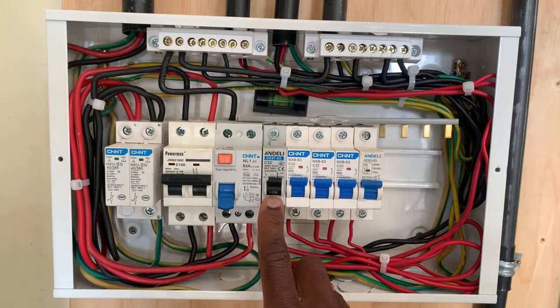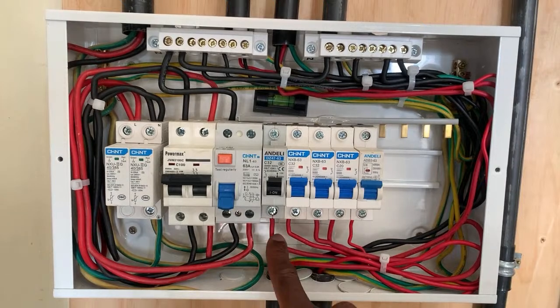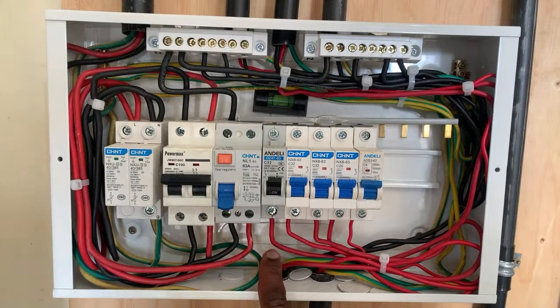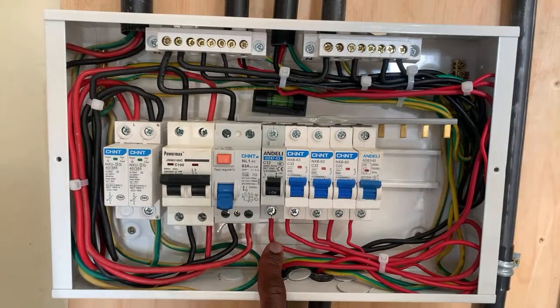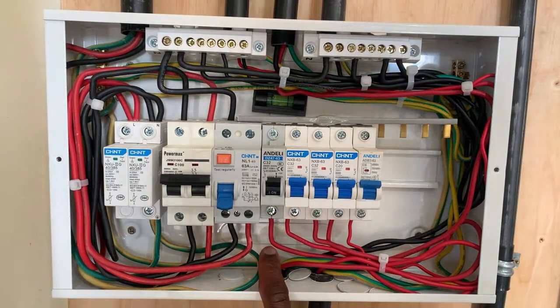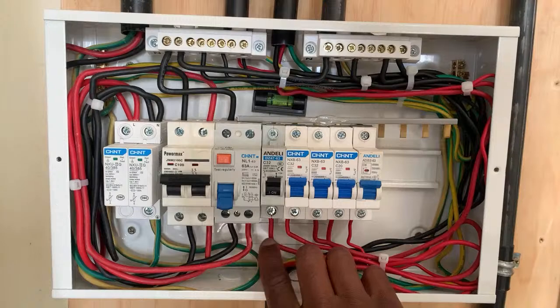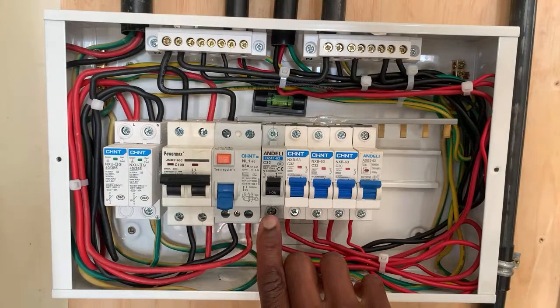The connection, like I said, must be done in a way that the screw is screwed on the cable and not on the insulation. If you screw on the insulation, then that circuit will struggle to complete itself. The complete circuit will not happen, or there will be a strain in current conductivity, which will indicate high resistance. High resistance will lead to what? Overheating of this cable.